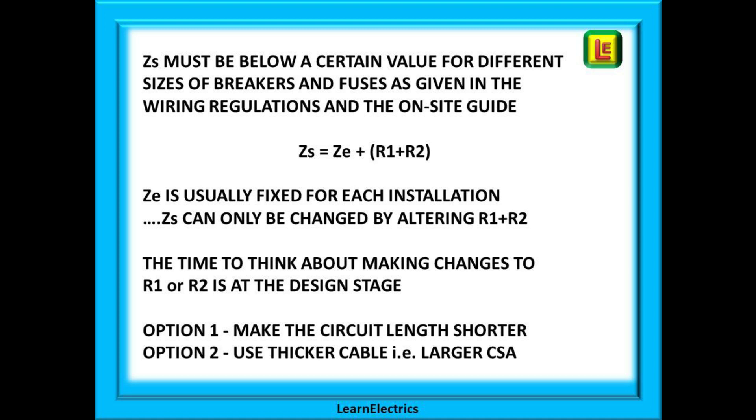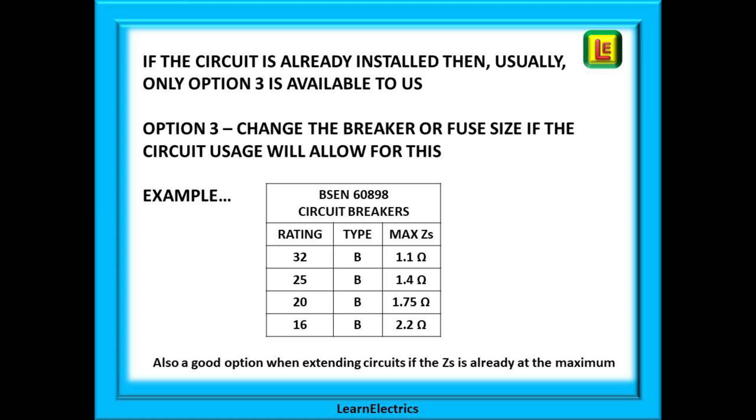Option one is to make the circuit shorter, but this is not always possible. If the water heater is upstairs that is where it is staying. Option two is to use thicker cables, a larger cross sectional area. This is usually the option that is taken up at the design stage. But remember copper cable is expensive so we don't want to make the size of the cable too big. If the circuit is already installed, already plastered in place and decorated, then we only really have option three as a choice. If the ZS is too high for the breaker size and we cannot change the cable, then why not change the breaker size to match the ZS. We can choose a breaker whose ZS is above the R1 plus R2 resistance that we have just measured.